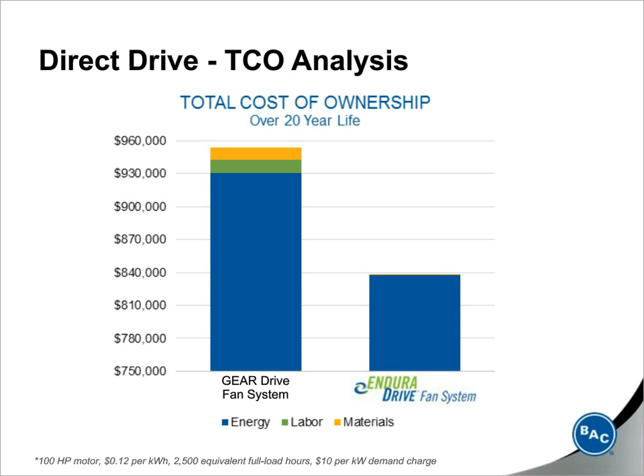Now, this chart can give you an idea of the overall savings that you can expect from the direct drive fan system. Again, we're going to assume 2,500 full load hours, 12 cents per kilowatt hour, a $10 per kilowatt demand charge, and a 100 horsepower motor. So over a 20-year life of the tower with the 100 horsepower motor, an owner can save $119,000 over a unit with a traditional drive system. This is going to greatly reduce your tower's total cost of ownership, in addition to reduced maintenance hours and less downtime.